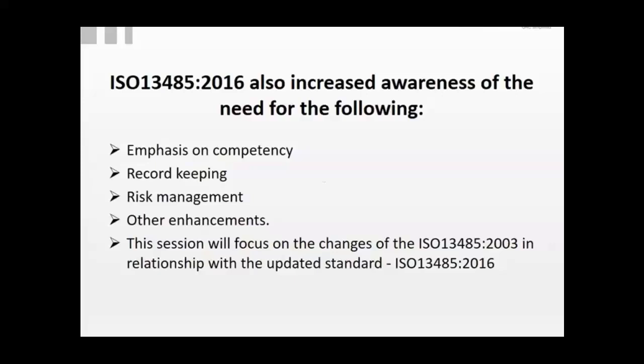How many times would that happen? How bad would it be if it happened, and will we be able to see it? You multiply these numbers. Again, criticality, and there are other things you can add to this that you find important. You come up with a number, and then you decide whether or not to tackle that problem at the design phase or some other phase of the product. That's one tool that you could use as risk mitigation for design. Other tools, like feedback from the field and how that is managed, are all part of this. I cannot emphasize enough the elements of risk management in the standard and at regulatory bodies. Risk management is very important, and again, I see it coming up everywhere.